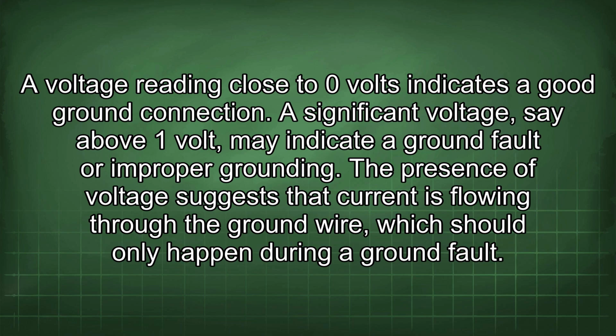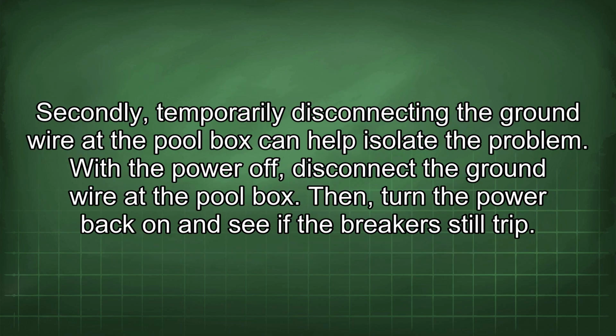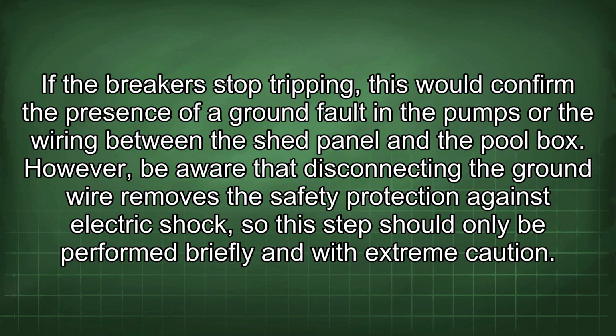The presence of voltage suggests that current is flowing through the ground wire, which should only happen during a ground fault. Secondly, temporarily disconnecting the ground wire at the pool box can help isolate the problem. With the power off, disconnect the ground wire at the pool box. Then turn the power back on and see if the breakers still trip. If the breakers stop tripping, this would confirm the presence of a ground fault in the pumps or the wiring between the shed panel and the pool box. However, be aware that disconnecting the ground wire removes the safety protection against electric shock, so the step should only be performed briefly and with extreme caution.